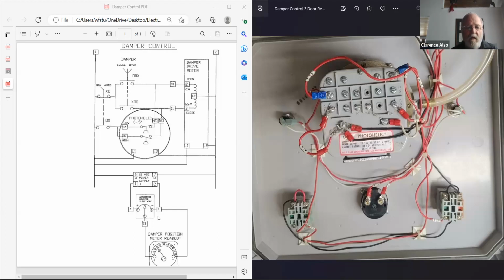Okay, so can you guys see this now, my arrow? Yep. Okay, this is a potentiometer, this is going to tell you where you're at. It's actually located inside this box right here. If I would have drawn that out correctly, I probably would have stuck that in there, but it was difficult for what we're doing here. So anyhow, this works. Whenever you do an open-close here, this wiper moves back and forth, and that tells you the position. It's always nice to know the position of your damper, especially when you're starting up and making sure it is open for purging.